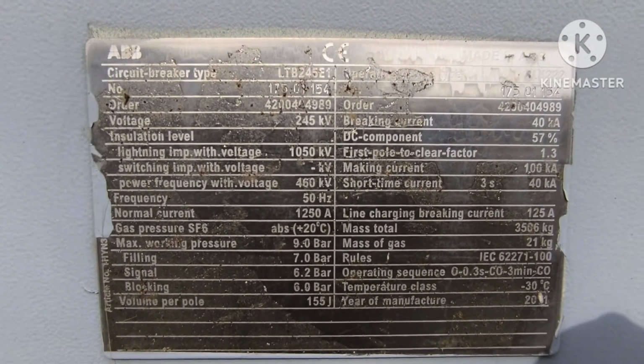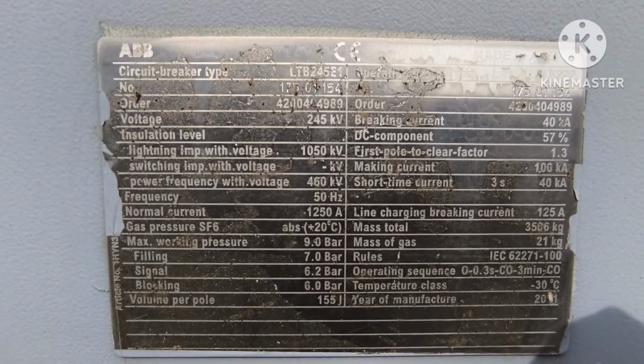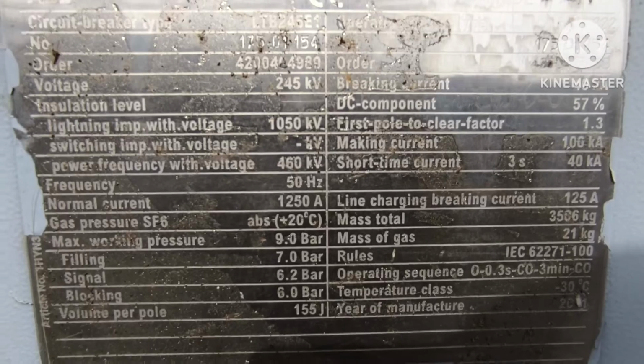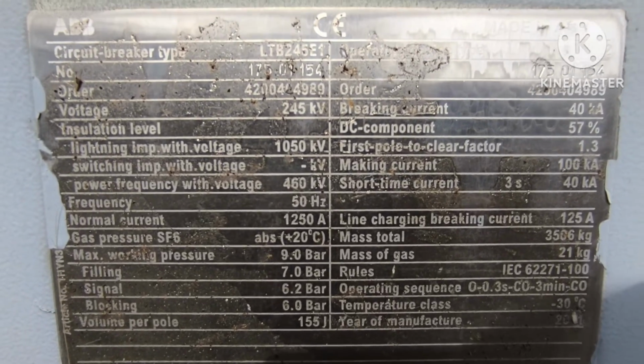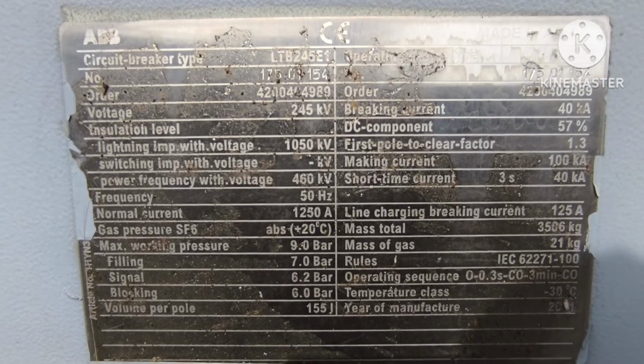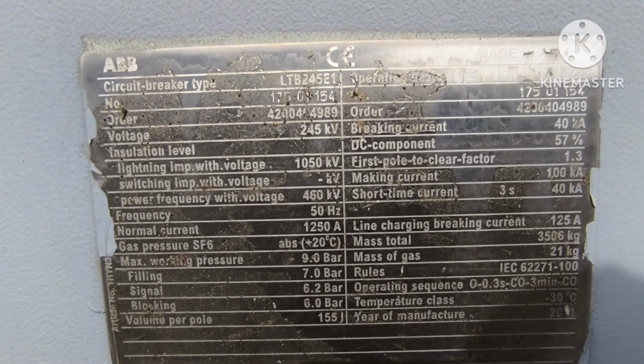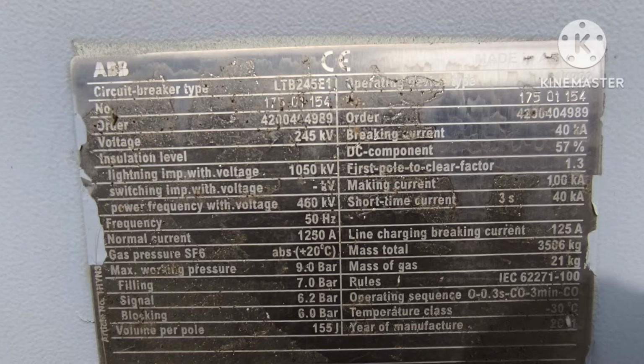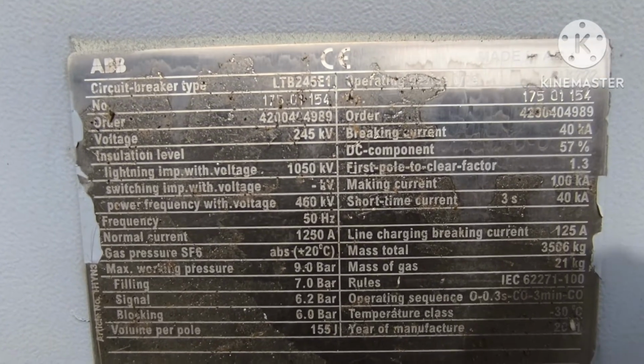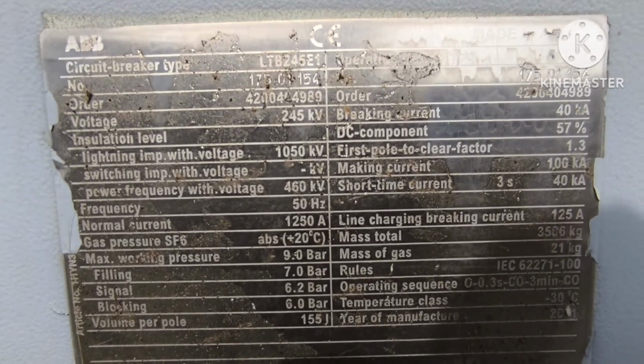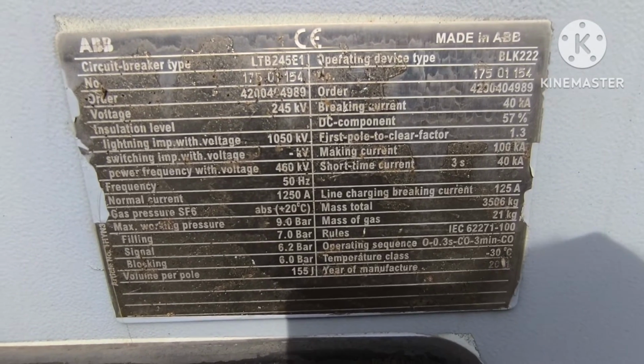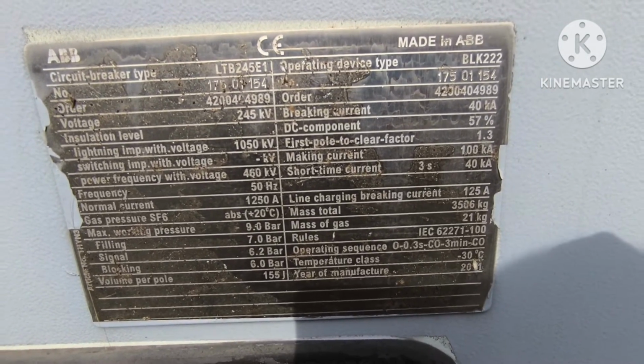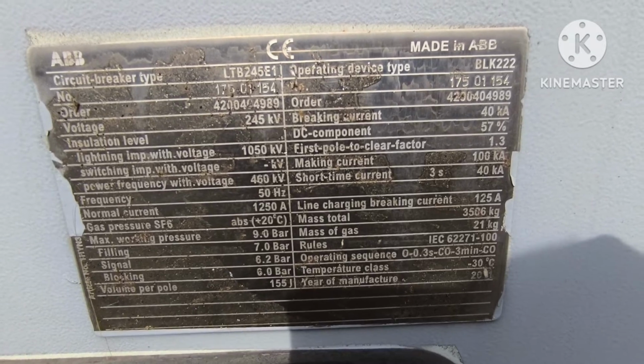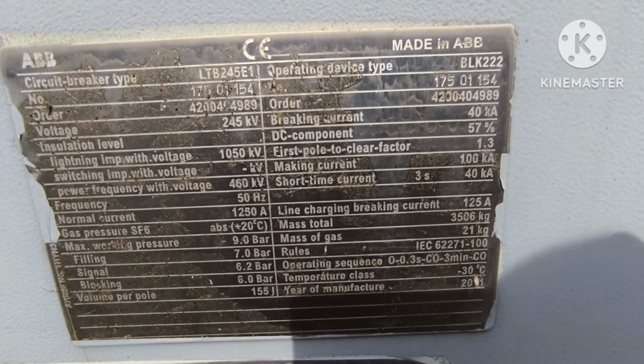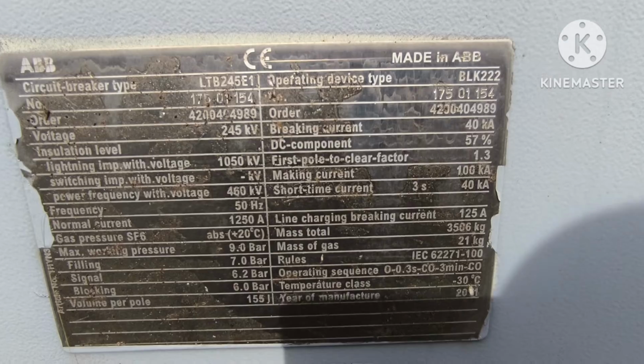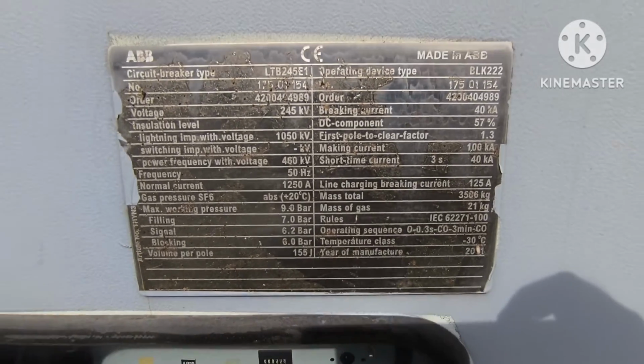Already it is theoretical part, we have already discussed those things. Highest system voltage will be 245 kV here, because for 220 kV the allowable highest system voltage is 245 kV. In 400 kV it will be 420 kV. The sequence is open, then 0.3 seconds, then close-open, then 3 minutes, then close-open. This type of sequence is suitable for auto reclosure of circuit breakers.